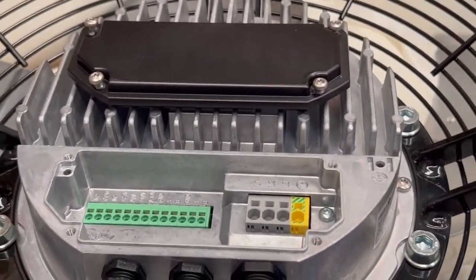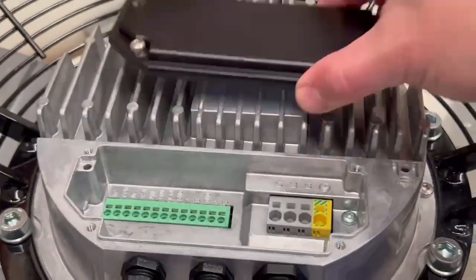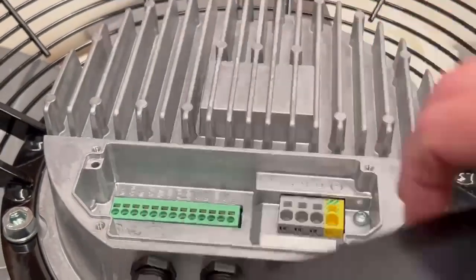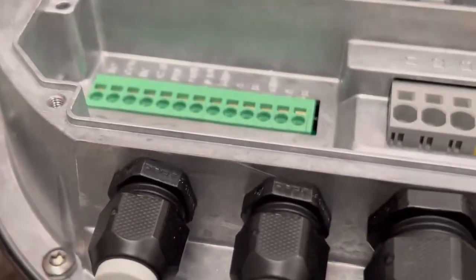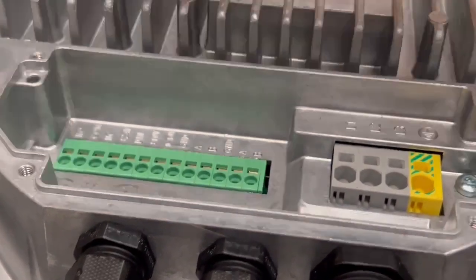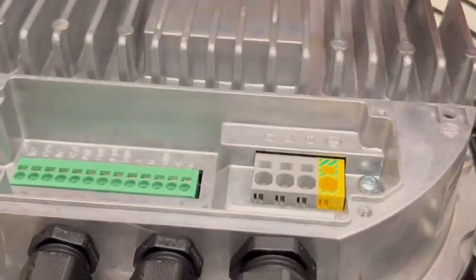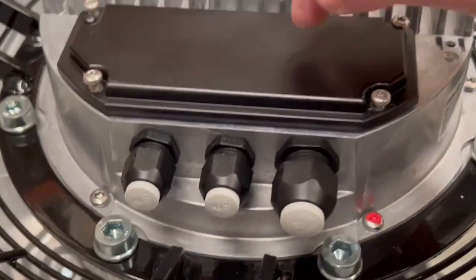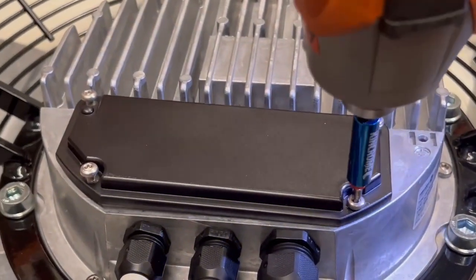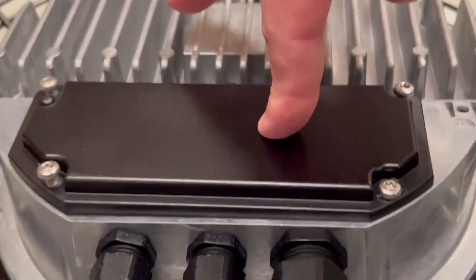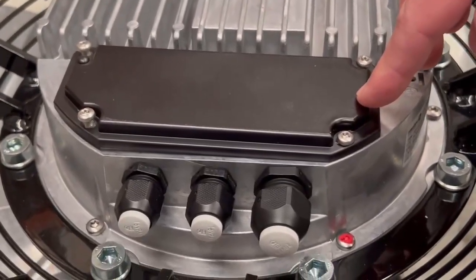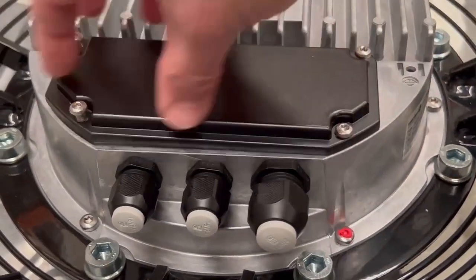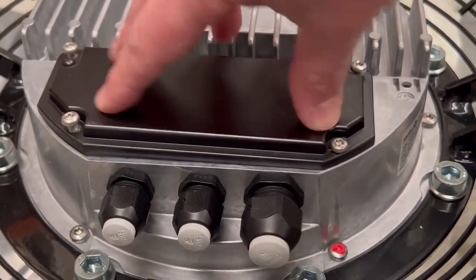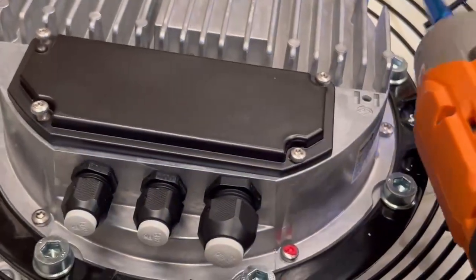Here on our EC fan, we can see this is a classic terminal cover. It's quite a simple, basic terminal cover with our IP glands coming in and then this IP rated cover. We can see there is a small lip around here, and that lip is pretty much what's protecting the water from getting in there, in combination with this rubber gasket that we can see underneath. Now, we don't have a lot to work with, and it's quite tempting to put the cover on, get your impact driver, and do it up and apply the pressure. But if you do that, you'll notice it's quite easy to get the terminal cover on at an angle, and even when we start to do these up, we might not get a perfect seal. So when we're doing sensitive covers up like this, I'd highly recommend doing them up loosely at first and then slowly inching them in so that we get a nice square seal, rather than banging in one and then the other with our impact driver.